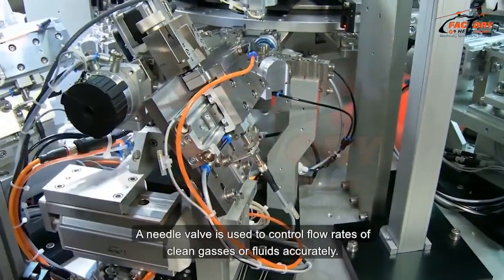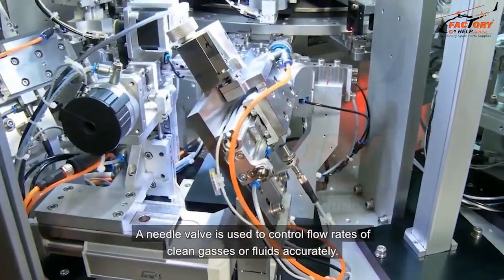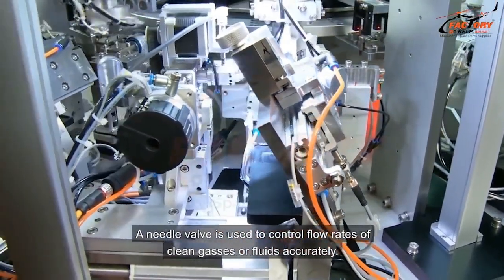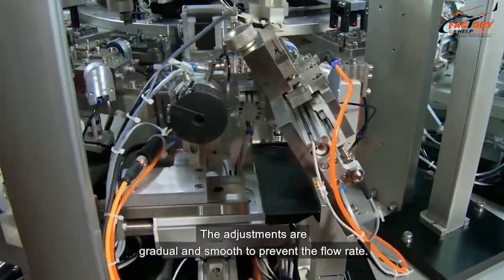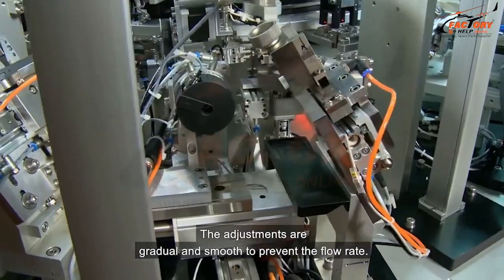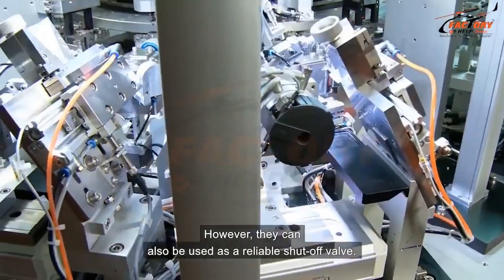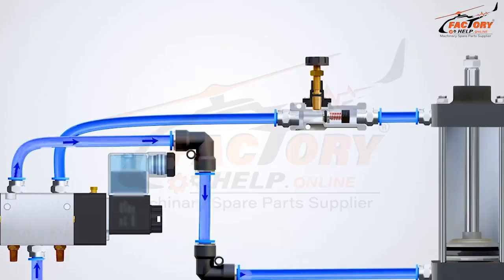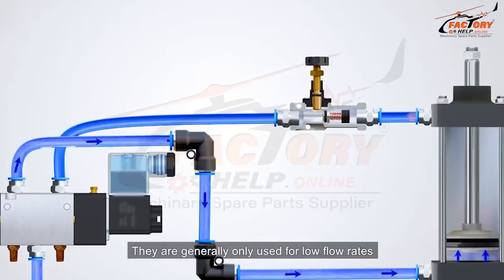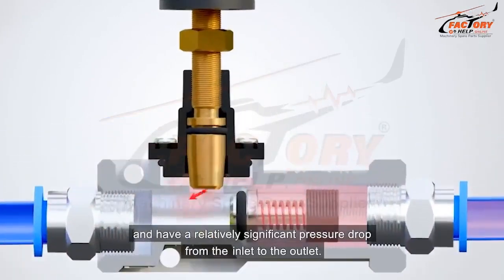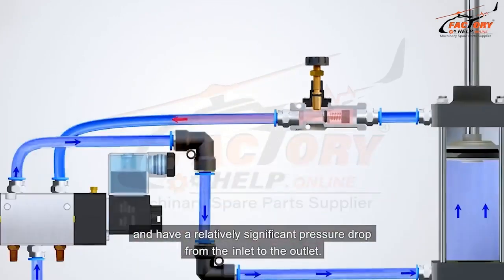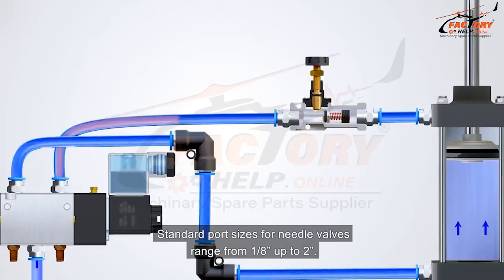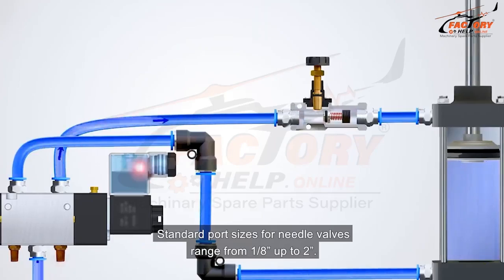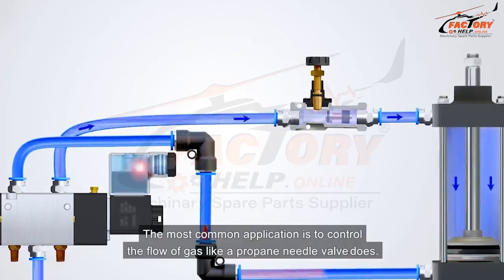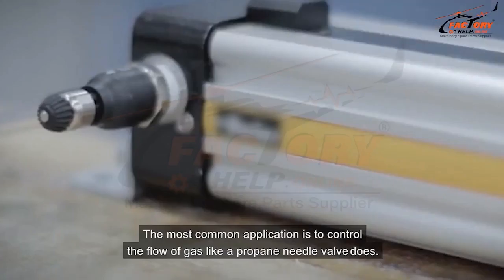A needle valve is used to control flow rates of clean gases or fluids accurately. The adjustments are gradual and smooth to prevent the flow rate. However, they can also be used as a reliable shutoff valve. They are generally only used for low flow rates and have a relatively significant pressure drop from the inlet to the outlet. Standard port sizes for needle valves range from 1/8 inch up to 2 inches. The most common application is to control the flow of gas like a propane needle valve does.